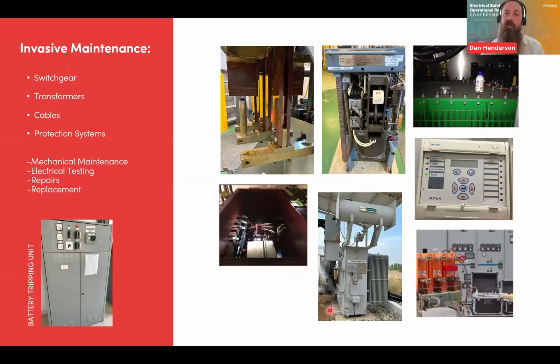As I mentioned before about thermography, it's a great tool, but only where you've got access to do things. So if you've got things like exposed conductor, overhead lines where you can actually get to, or cast resin transformers where you've got access, or where you've got thermal imaging windows supplied. Obviously, it's not recommended to remove covers live just to do thermography, because you're giving rise to danger just to do a thermal survey. And if you're not doing that, you're taking a thermal survey of a cover, which you're not going to get anything from. So if that's the case, it might be an opportunity within your shutdown to retrofit or look at your design and include thermal windows as part of your design if you're putting new boards in, or retrofit things like that in your maintenance programs, just to make your life and your maintenance team's life a bit easier.